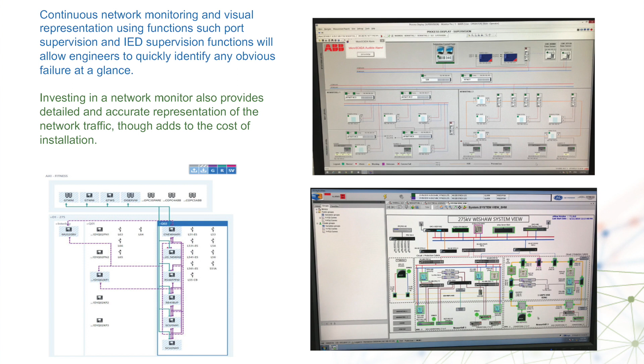Enable continuous monitoring. You might not be able to continuously monitor every aspect of your communication network, but you can enable port supervision, which I definitely recommend. A port supervision screen, like the ones shown here - we have two SCADA systems in this setup, and you can see both deploy port supervision, some 61850-based, some SNMP-based. But beyond port supervision, they also take individual IED data qualities and show you if there's a time sync failure, a failure in signal quality, or if the IED itself isn't healthy. All these parameters are available as data attributes in the logical nodes about IED health, so why not use it?